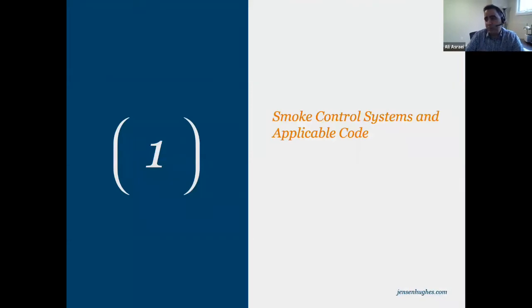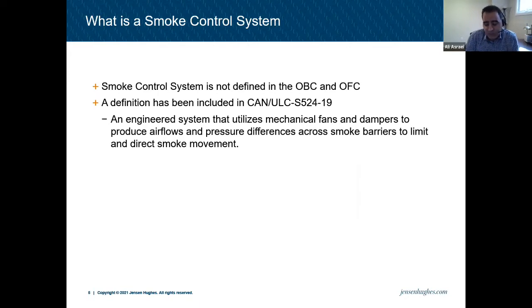So let's talk about a smoke control system and applicable code first. Smoke control system is not a defined term in the Ontario Building Code or even the fire code. A definition has been included recently in CAN/ULC-S524 2019, which is not really applicable to it, but since we don't have any definition, I thought maybe it's a good thing to add it here. They call it an engineered system that utilizes mechanical fans and dampers to produce airflows and pressure differences across smoke barriers to limit and direct the smoke movement. So any system that does that is technically considered a smoke control system. And in the lack of a definition in the OBC and OFC, we're using it from CAN/ULC-S524.